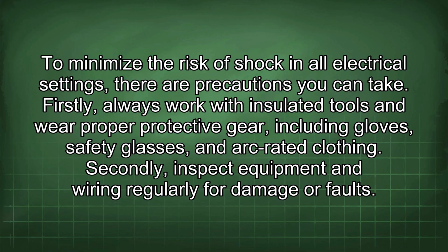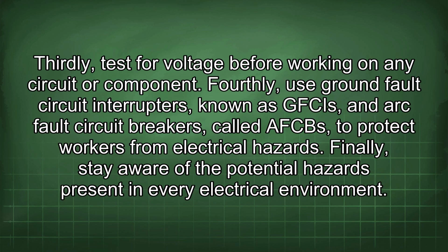Firstly, always work with insulated tools and wear proper protective gear, including gloves, safety glasses, and arc-rated clothing. Secondly, inspect equipment and wiring regularly for damage or faults. Thirdly, test for voltage before working on any circuit or component. Fourthly, use ground fault circuit interrupters, known as GFCIs, and arc fault circuit breakers, called AFCBs, to protect workers from electrical hazards. Finally, stay aware of the potential hazards present in every electrical environment.